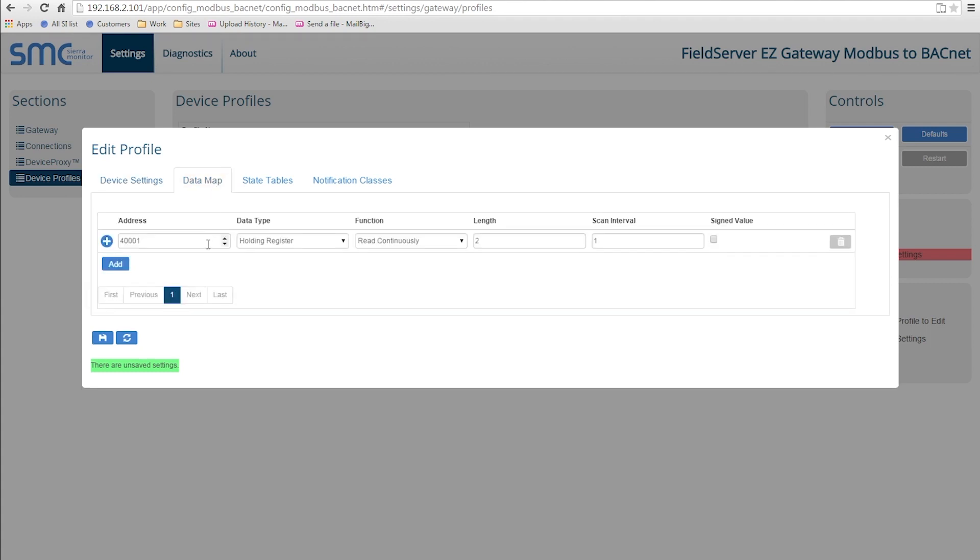On the Data Map tab, you can map Modbus registers to BACnet objects. On the Modbus side, you can specify the Modbus address, data type, function, length, and scan interval.